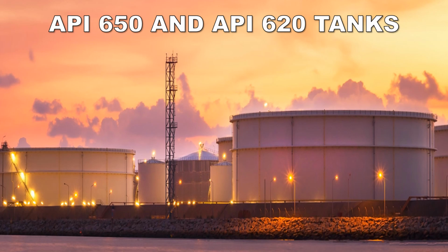Both tanks are used for storage, can be constructed from carbon steel, stainless steel, or nickel alloys, and inspection is required for both tanks. The major differences come from the configuration, size, pressure, and temperature parameters. Oil, gas, chemicals, water, and biofuel storage can use the API 650, while storage for cryogenic or LNG tanks requiring high pressure need the API 620.